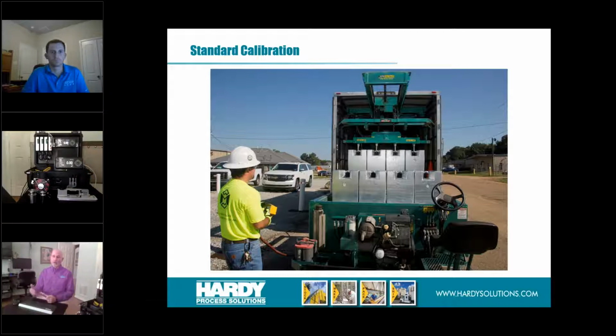On top of those two concerns, there's also the cost of getting all this equipment out on site, the cost of the technician himself, but a hidden cost behind this is the productivity cost. Whenever you're doing this, your scale is not in service. Let's say you have 3 blending scales in your facility - every time you go to calibrate that scale, 1/3 of your productivity is shut down. So if that's a half day or full day of service, you've got 2/3 of your productivity - 1/3 is gone, you're only operating at 2/3 capacity.